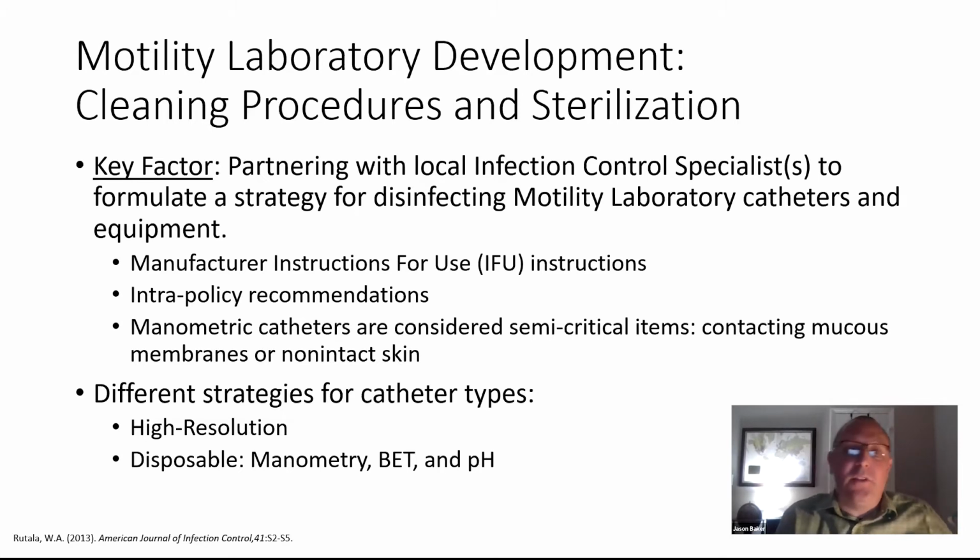Some people have this transported to a hospital base. Some people have some local infection control. Some are central. All of that involves some intra-policy recommendations. But ultimately, the manometry catheters are considered semi-critical items. That means they contact mucosal membranes and non-intact skin, in the nasal passage and in the anal rectum. So that means it needs high-level disinfection. There are different strategies depending on the type of catheter that you're using. If it's high resolution, it needs to go through the whole process of infection control.